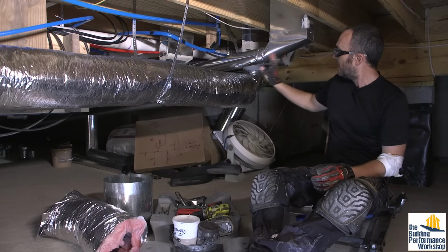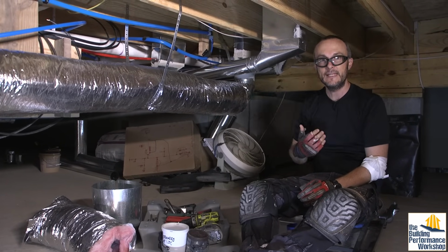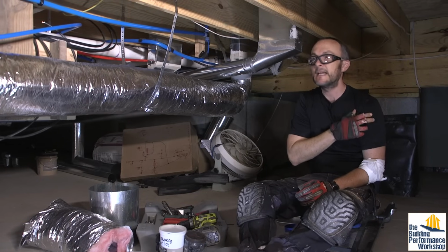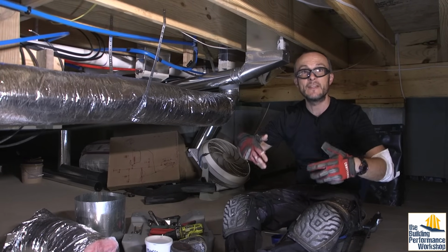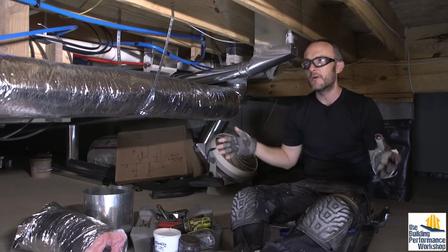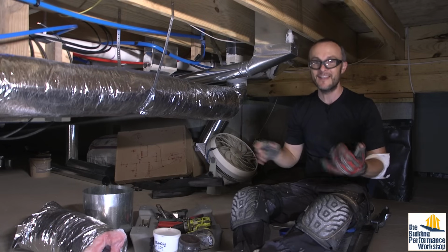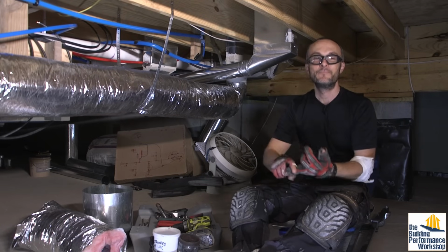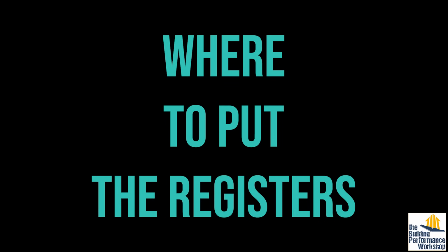I'm insulating these ducts because I don't want the outside of them to be wet when we're air conditioning. So the ventilation system does not need to be insulated past the ERV on this side of the house because all of the air inside of it will be roughly the same as the temperature inside this conditioned crawl space. This is not a vented crawl space. This is a mini basement. I wanted this space to be for services, and you'll see as we go through here, it's getting pretty crowded in here with just the things that we have here. Ductwork, plumbing, electrical lines, all the equipment, things like that.